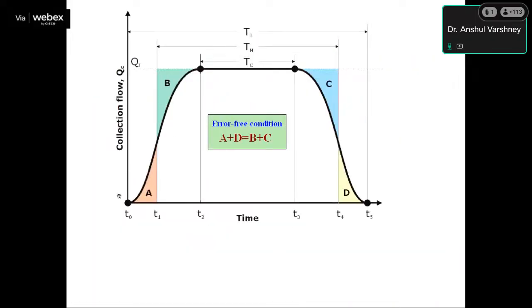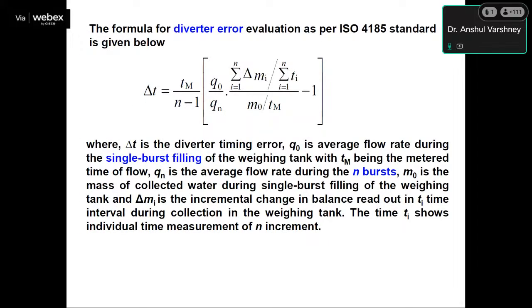Basically, if you are considering the collection flow from T0 to T5, then for an error-free condition, this area should be equal to this area. A plus D should be equal to B plus C. If it is not equal, the diverter error should be kept as minimal as possible for an error-free transition. So this is the mathematical formula. With the help of this standard formula, which is given in ISO 4185, we are minimizing the diverter error at our facility.